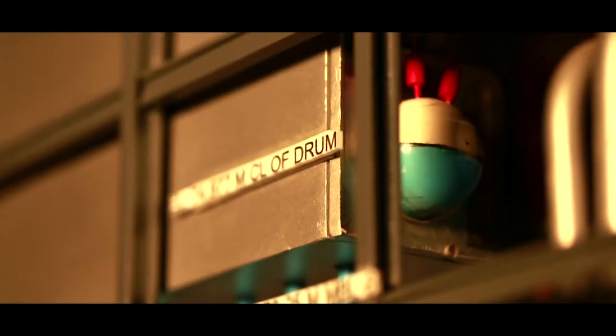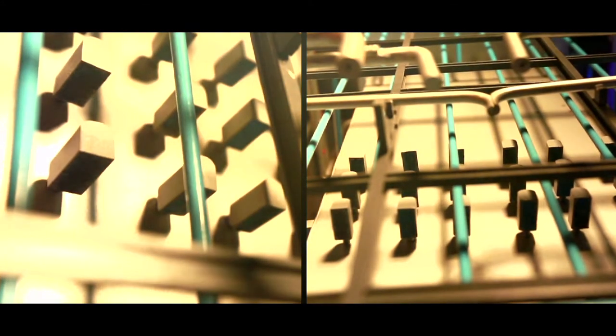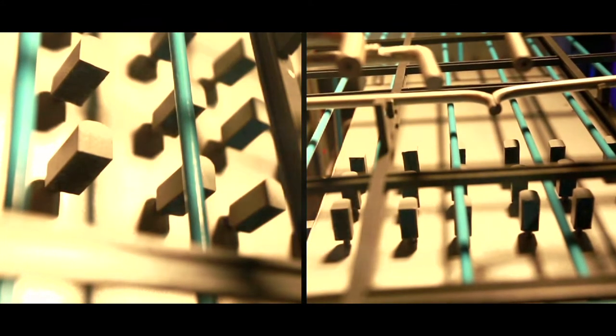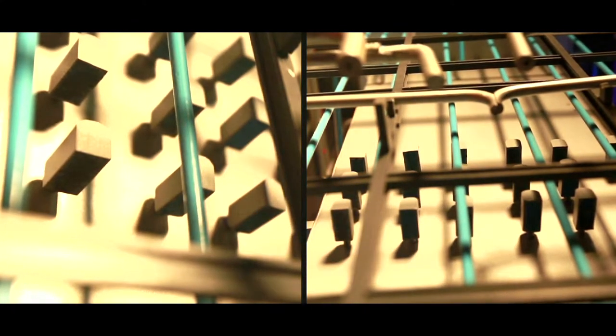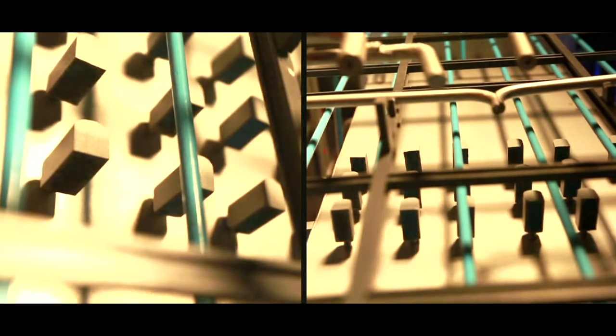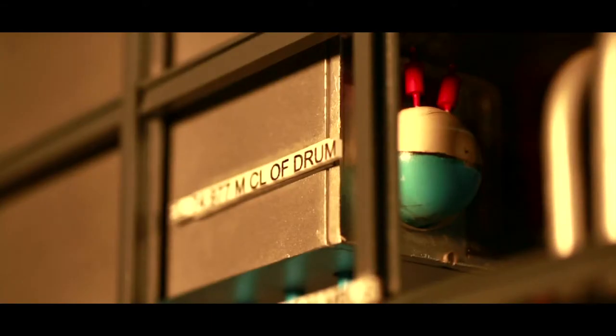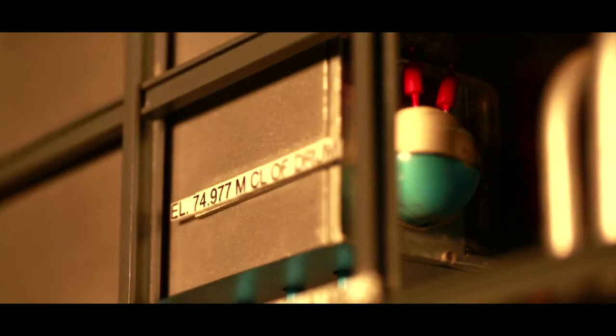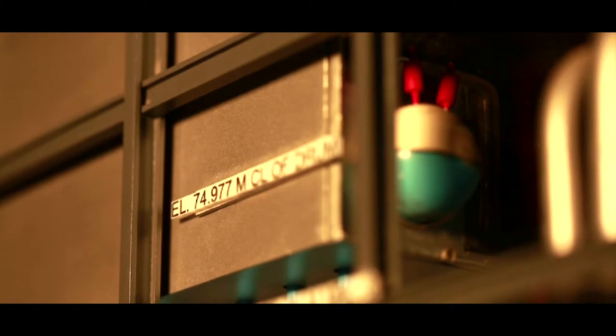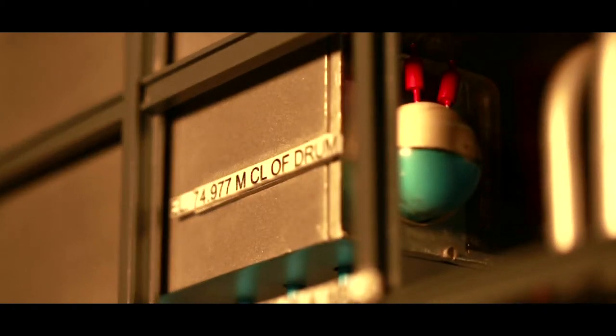From the drum, water flows through downcomers to the furnace's front wall water lower inlet header through BCW pumps. These BCW pumps force circulation of water through the furnace's water walls. As rising water helps in absorbing the generated heat in the furnace, the mixture of water and steam is sent back to the drum for separation. The separated steam follows the steam circuit and the water is returned to the water side of the boiler drum for recirculation.